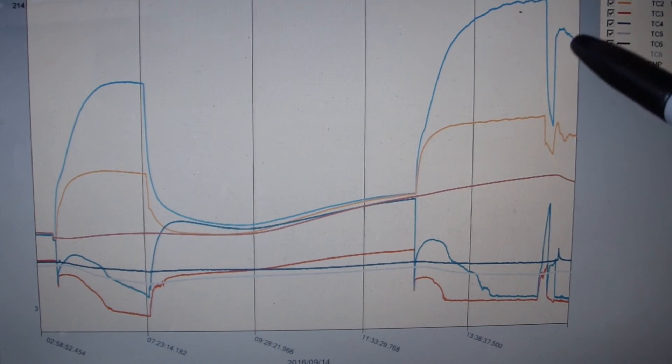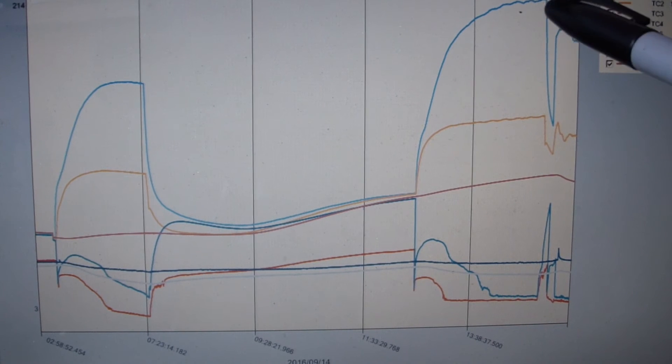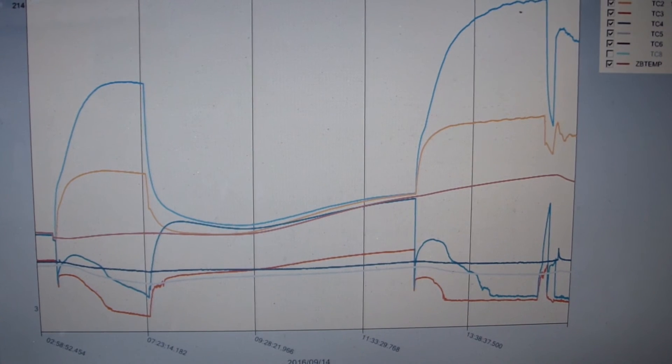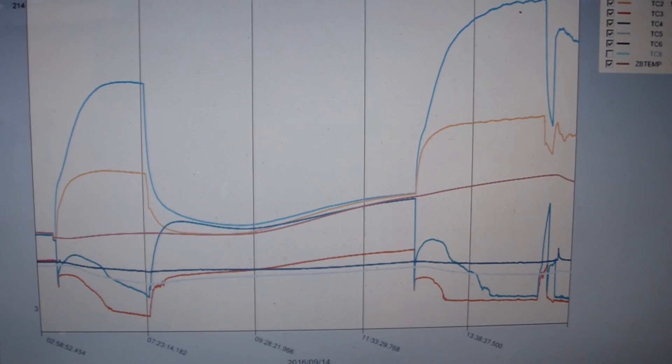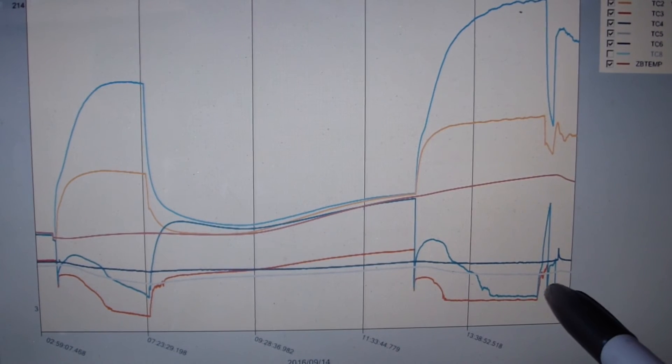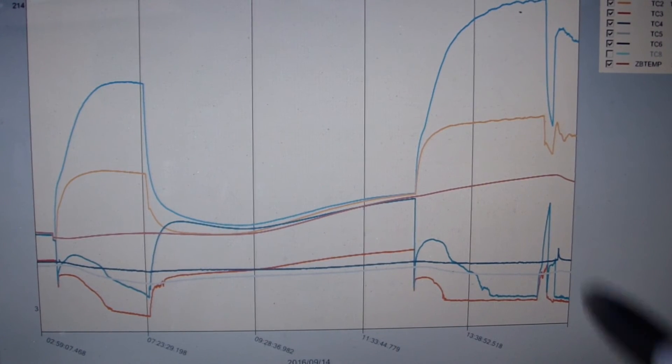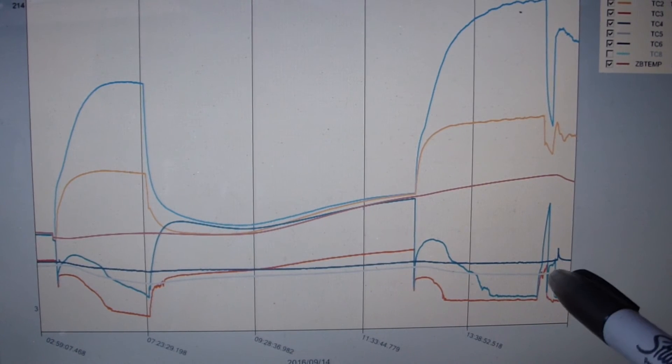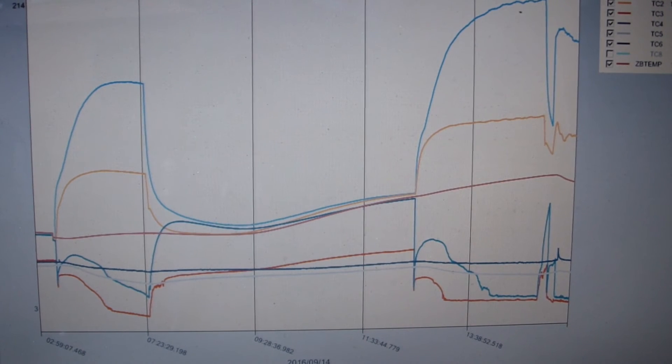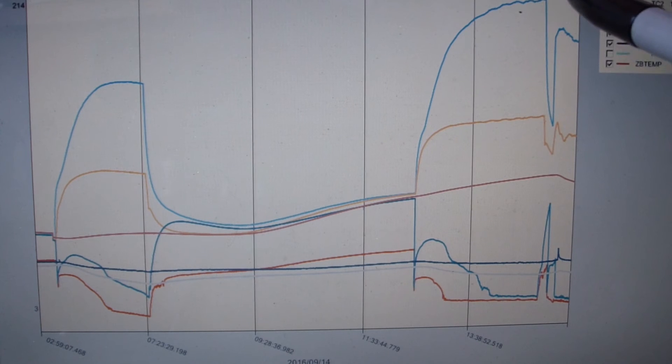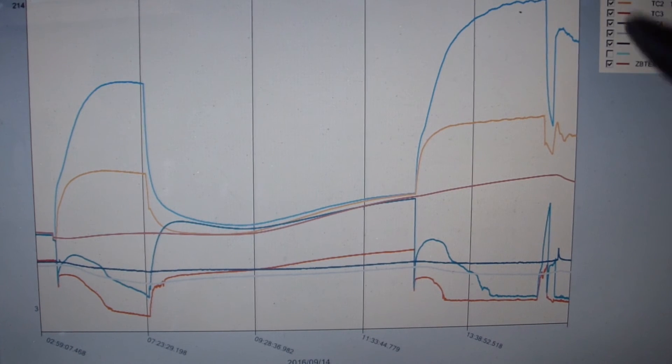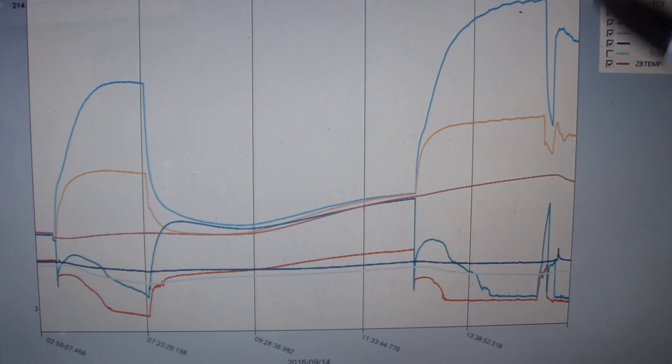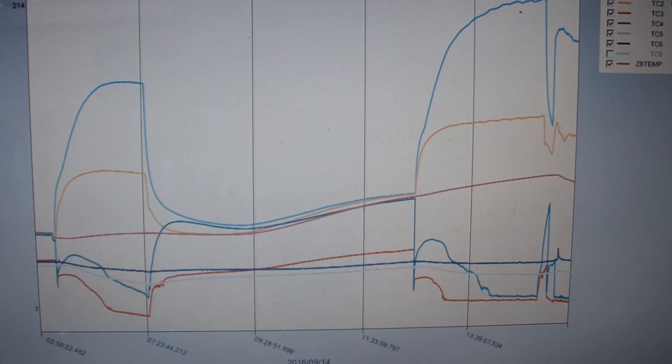It's in about high 120s, 130s on subcooling. That's right where I opened the door. Whenever I whip the door open, I'm in a sudden rush of air and the discharge superheat dropped, the subcooling temperature dropped, the superheat value before the compressor but after the heat exchanger rose very high, and then things started to settle back out.